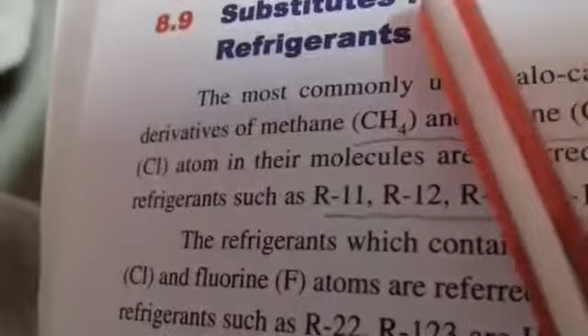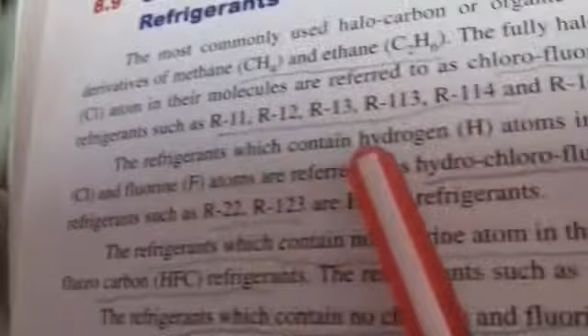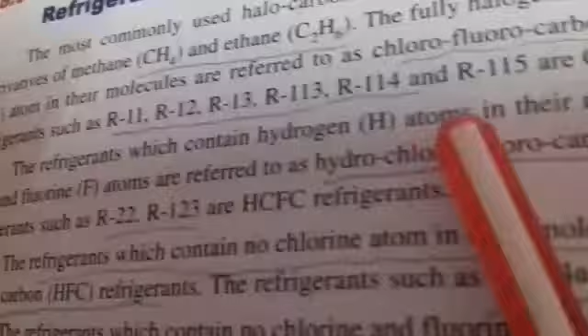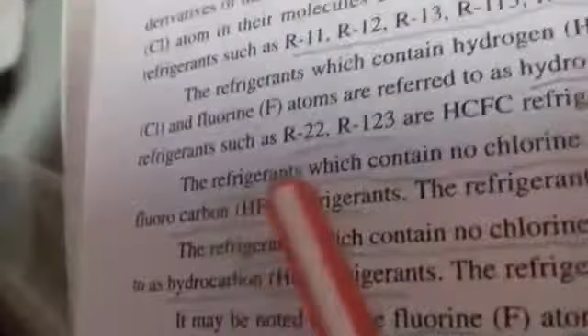chlorofluorocarbon. Now the refrigerant which contains hydrogen atoms in its molecule along with chlorine and fluorine atoms is referred to as hydrochlorofluorocarbon HCFC refrigerant. The refrigerants such as R22 and R123 are the HCFC hydrochlorofluorocarbon refrigerants. The refrigerant which contains no chlorine atom in its molecule is referred to as a hydrofluorocarbon HFC refrigerant. The refrigerants such as R134A, R152A are the HFC refrigerants.